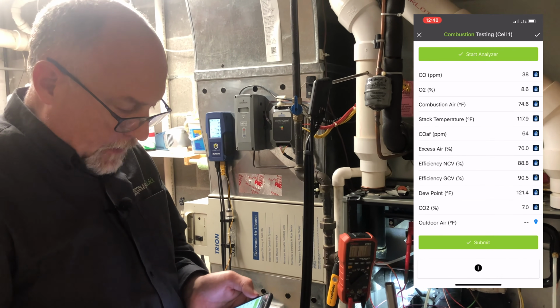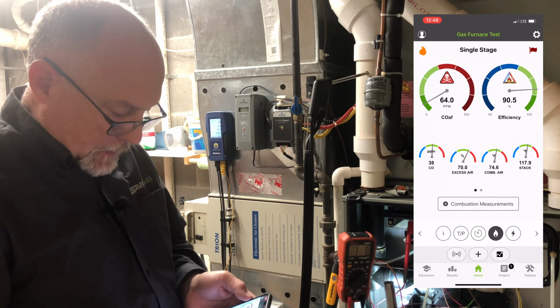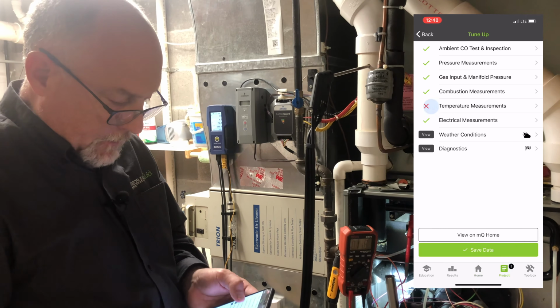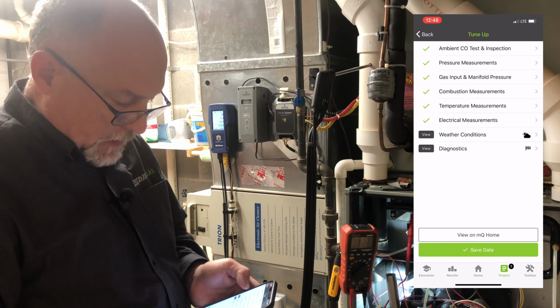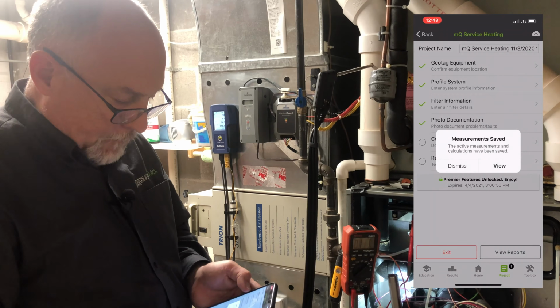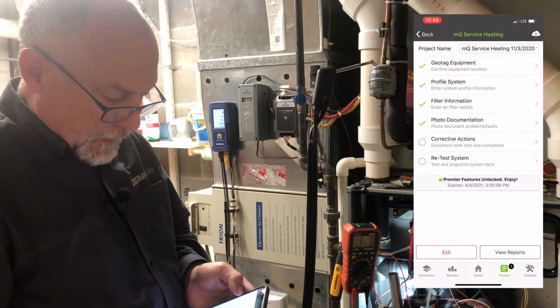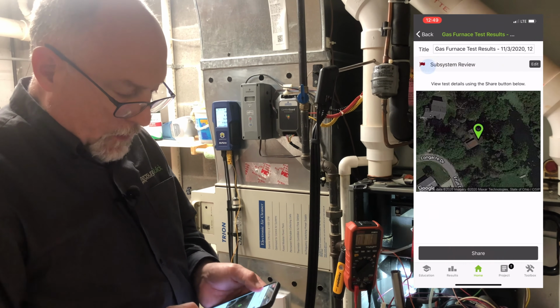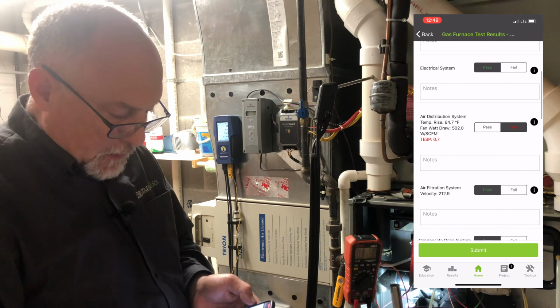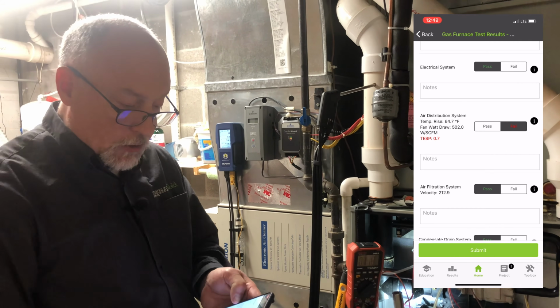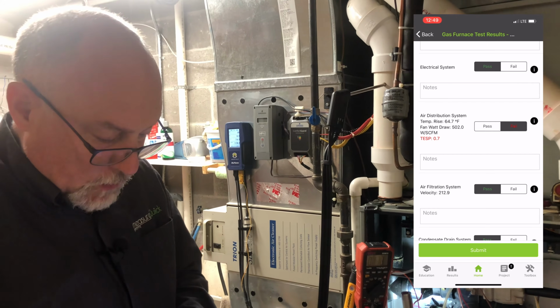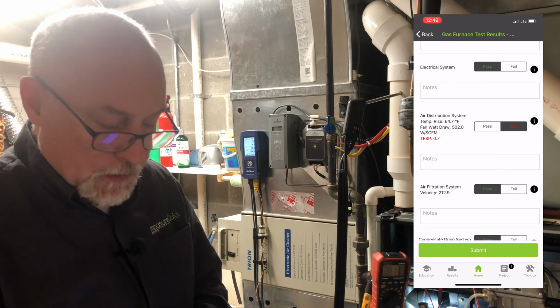All right, we got our values captured, submit, and then I'm going to go in here, project, temperature measurements, grab those, hit submit, save the data, view, and hit share. Now I notice here I'm failing on a subsystem review, and it's because my total external static pressure is at 0.7 inches, which is just above the threshold on here for this appliance.